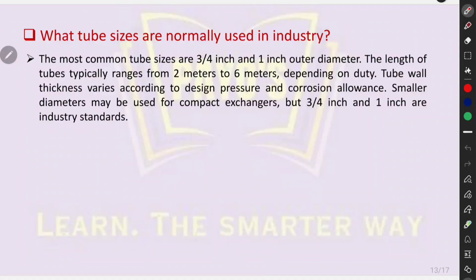What tube sizes are normally used in industry? The most common tube sizes are 3/4 inch and 1 inch OD. The length of tubes typically ranges from 2 meters to 6 meters depending on duty. Tube wall thickness varies according to design pressure and corrosion allowance. Smaller diameters may be used for compact exchangers, but 3/4 inch and 1 inch are industry standards.